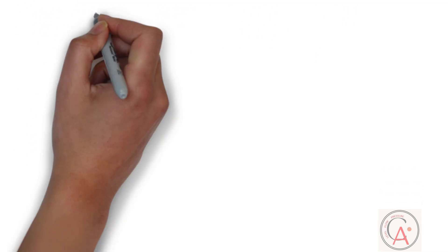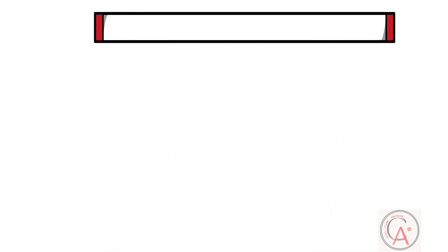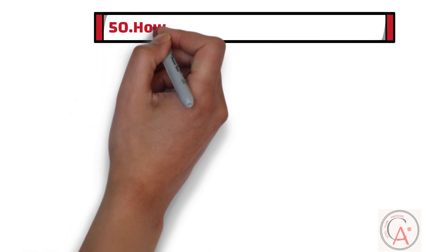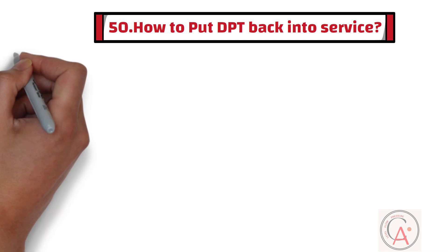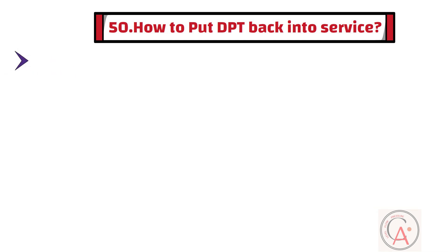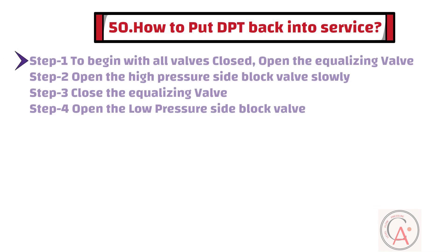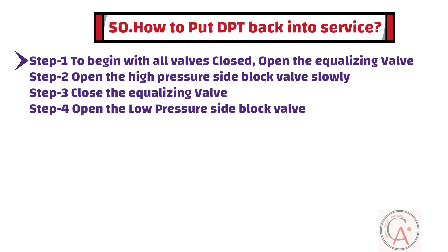Question 50: How to put DPT back into service? To put DPT back into service, begin with all valves closed, then open the equalizing valve. Then open the high pressure side block valve slowly. Then close the equalizing valve. At the end, open the low pressure side block valve.